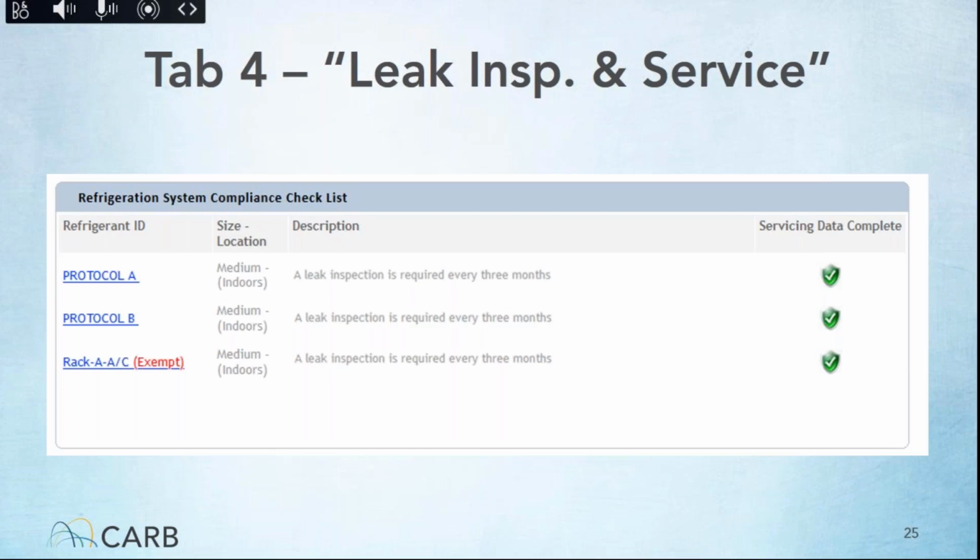There's been a few times in an inspection that somebody's had a registered medium system, and they've actually had 4 150-pound independent circuits all right next to each other. So I've had to follow the piping, and sure enough, none of them are connected at all. And I've kind of given the guy the news that you actually should be registered as a small, not a medium.